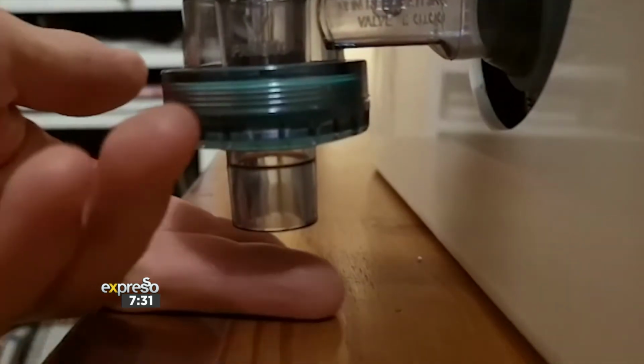And then it gives the patient a chance to breathe out after giving them the breath, so that the patient can decide when to breathe on an ICU type ventilator. Ours isn't that. Ours is an emergency ventilator, so the patient is helped to breathe. It gets the steady airflow as it is provided by the device, that's why it's called mandatory, because it automatically gives you the breathing.